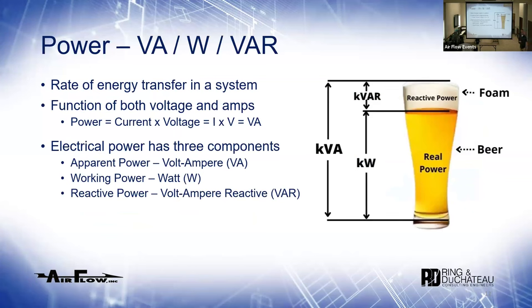Talking about power — I don't know how many of you have seen the beer analogy; it's definitely an electrical thing. The term power, P equals IV, or in units VA, is called a volt-ampere. It's highly creative — what's power? Volts times amps, so we call it a volt-ampere. A VA is basically the full amount of power. When a power plant makes power, the generators are making VA — the full Monty. Working power is what's actually used up by a motor, by a light bulb.